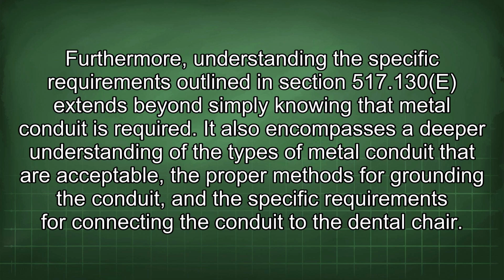Furthermore, understanding the specific requirements outlined in Section 517.130 extends beyond simply knowing that metal conduit is required. It also encompasses a deeper understanding of the types of metal conduit that are acceptable, the proper methods for grounding the conduit, and the specific requirements for connecting the conduit to the dental chair.